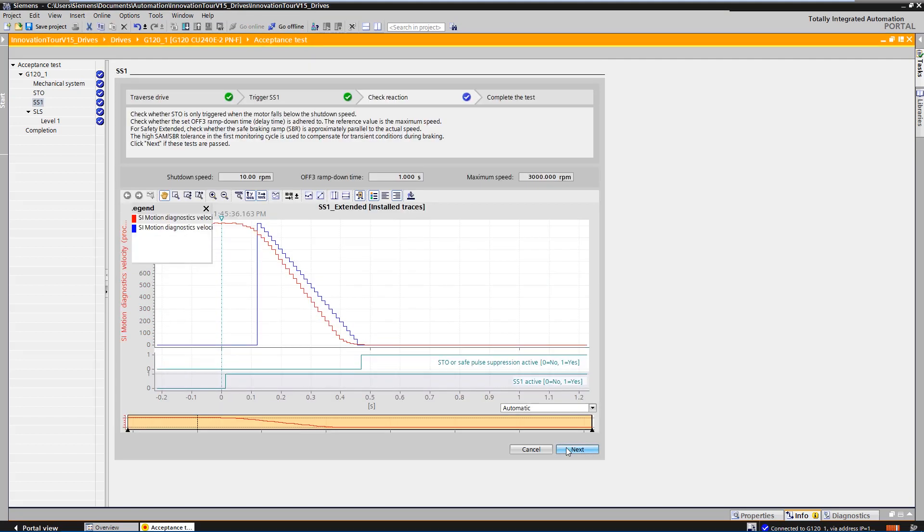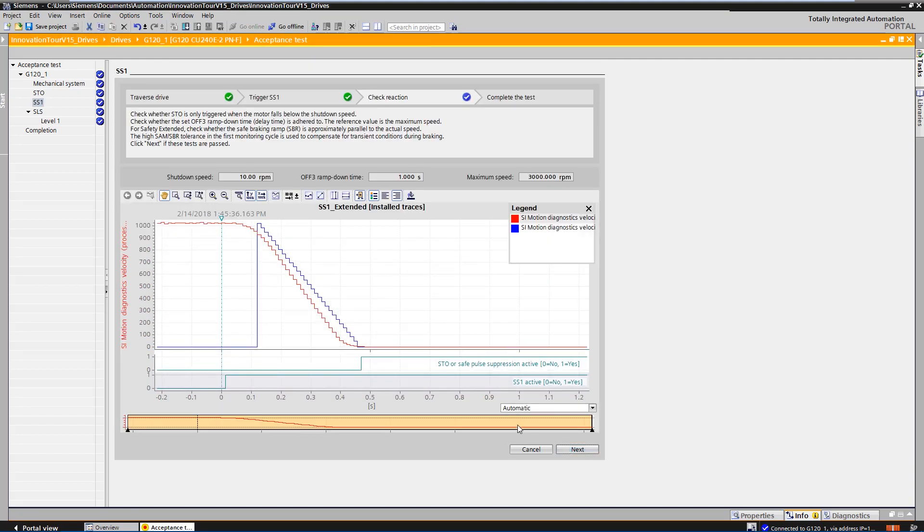The acceptance test automatically created a trace with the most important parameters. The trace can be used to check that the drive is decelerating in accordance with the specifications and that the state of the safety signals is correct.